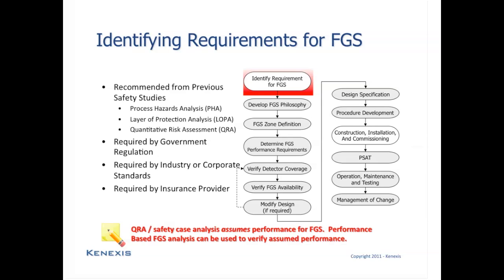Okay, going through each one of these steps in a little bit more detail in order to provide a more sound basis for what occurs during the various phases of the FGS safety life cycle. Again, the first step in the FGS safety life cycle is the identification of the need to perform a fire and gas system design. There are a lot of studies, a lot of formal process hazards analyses that will result in the recommendation to implement or possibly the recommendation to set targets for the fire and gas system design.